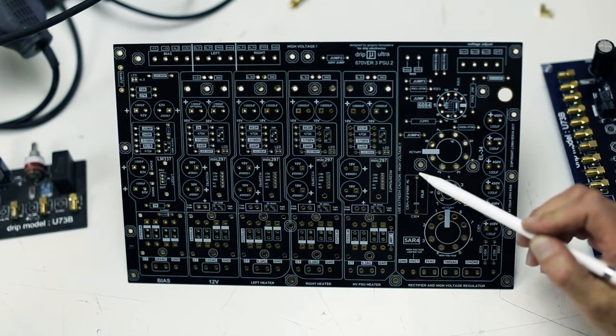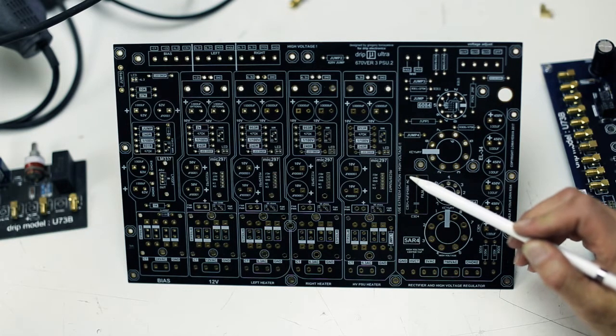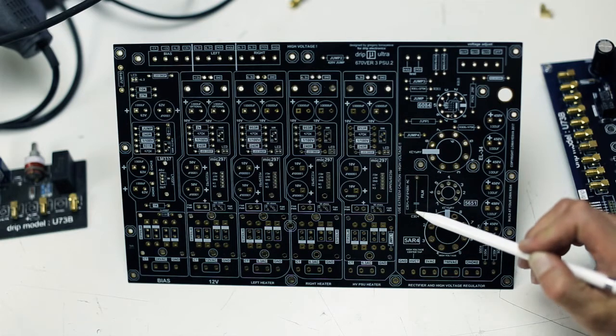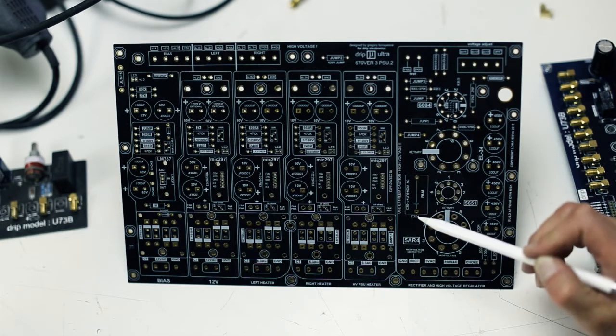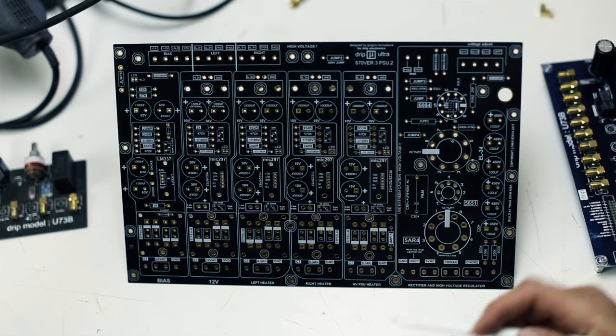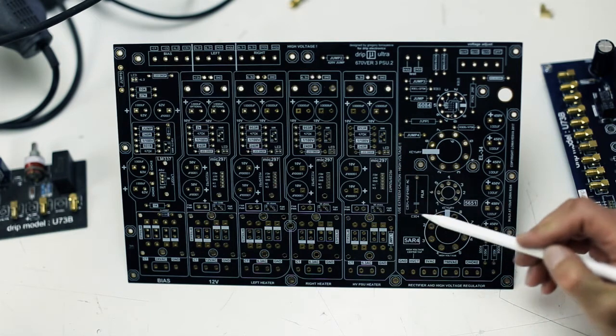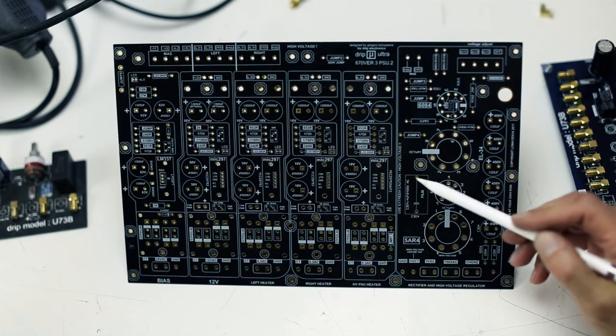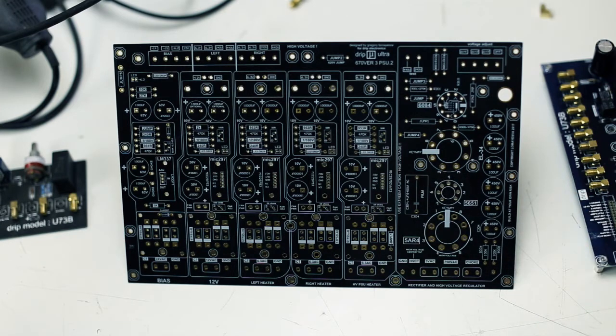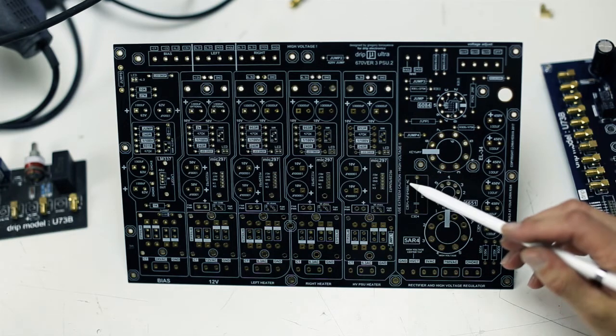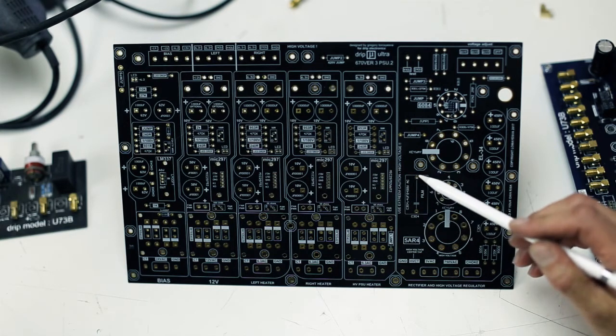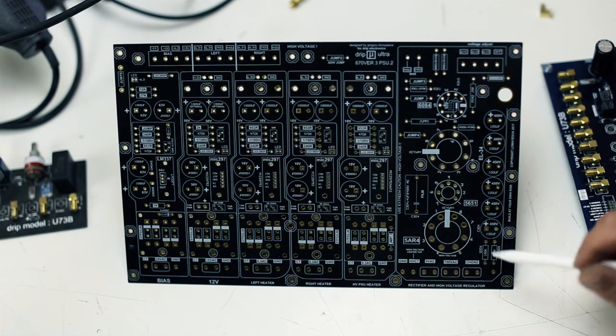Here you can install the oil-filled AC motor run capacitor by connecting wires into these spots. Capacitor technology has advanced so much that the high pulse WIMAs work great here, rated for 600 volts DC, and there are some specifically designed for AC that fit a 27.5 millimeter footprint.